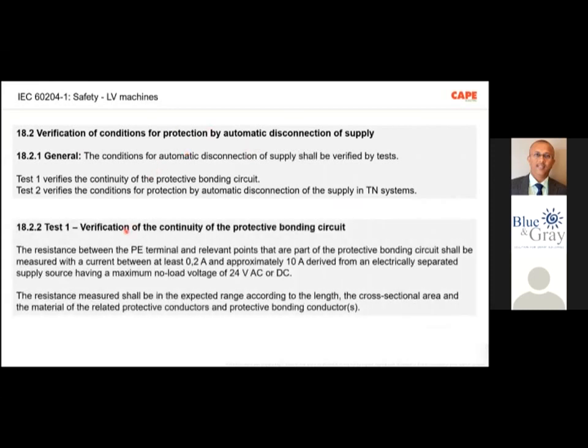And the first test, you see, is verification of continuity of protective bonding circuit. What is a protective bonding circuit? Every building, every low voltage installation, is supposed to have a protective bonding circuit, or equipotential bonding circuit, or protective equipotential bonding circuit. Somebody had asked what is the meaning of protective, of bonding, and of equipotential. Bonding is a connection. Equipotential means there is no potential difference between two parts. Protective is safety. Protective equipotential bonding means that for the purpose of safety, you are making an equipotential bonding.